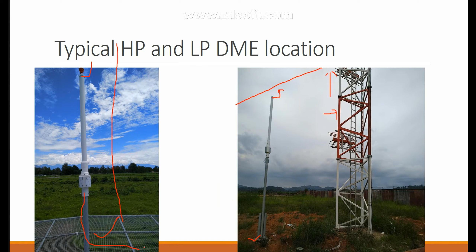So one more thing is these surge protections. This is RF surge protection, wherever the RF cables go from the antenna inside the hut to the equipment. Basically there are three cables total: one is feed and two are monitors. At these locations, at the monitor end, we will put the RF surge protection devices, and we will earth the body of these RF surge protection devices to the common earthing.